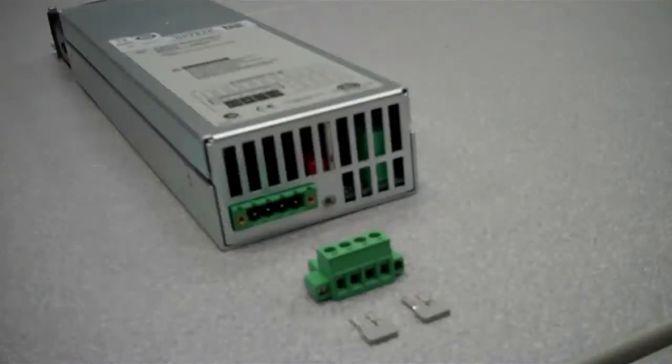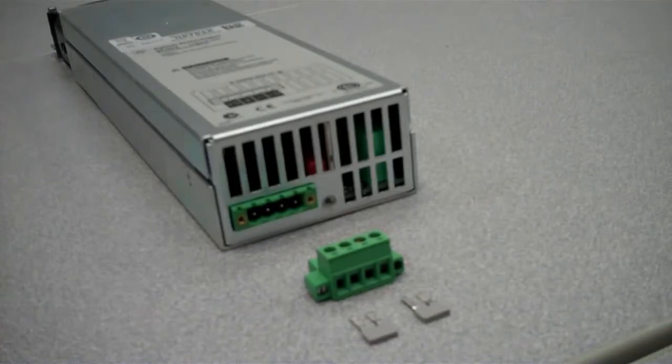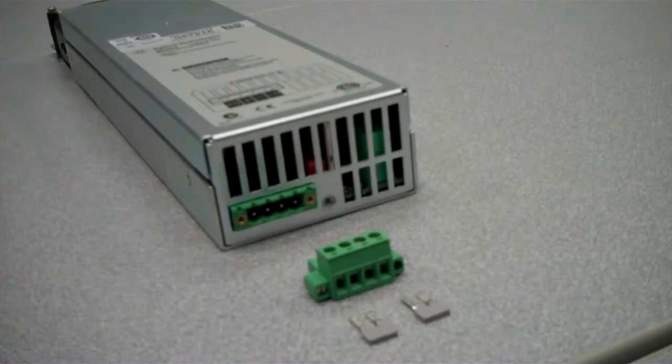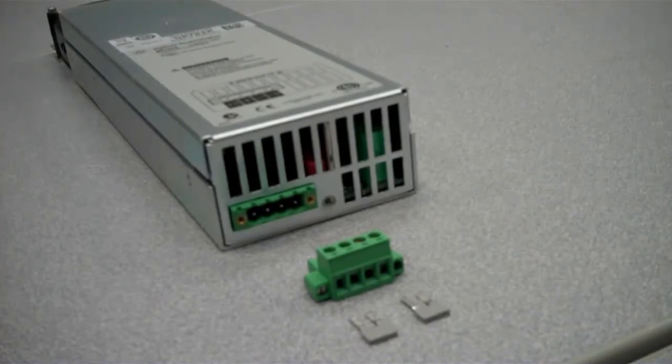This is the first connector we're going to talk about. This is the most common connector for all modules with 12 ampere or less output current. It's very pervasive in this family. We're not going to mention the specific models that use it because we'll mention the models that don't use it when we talk about the other connectors.